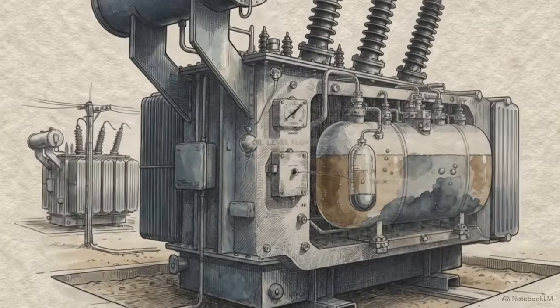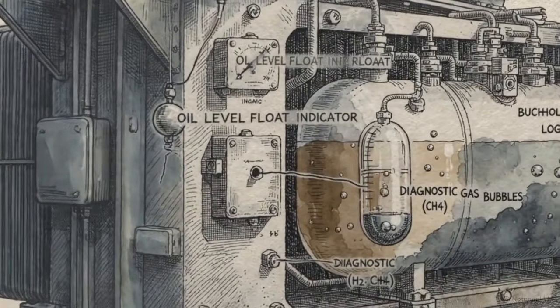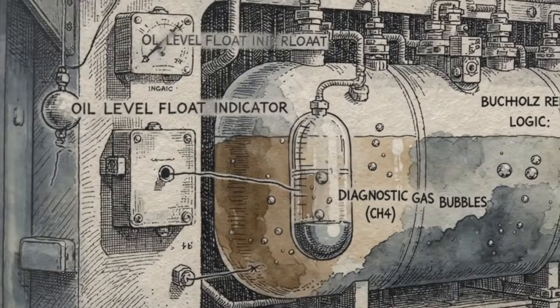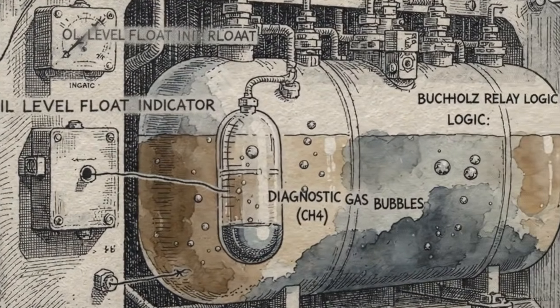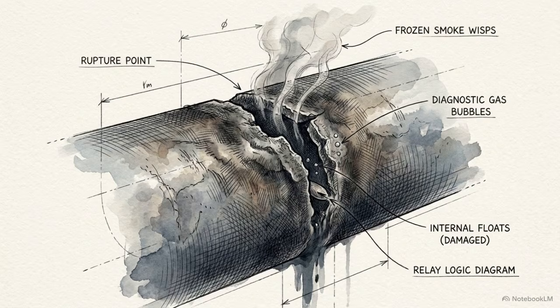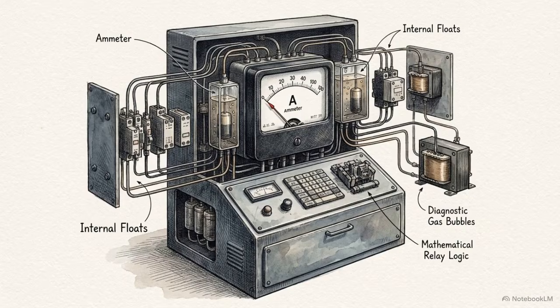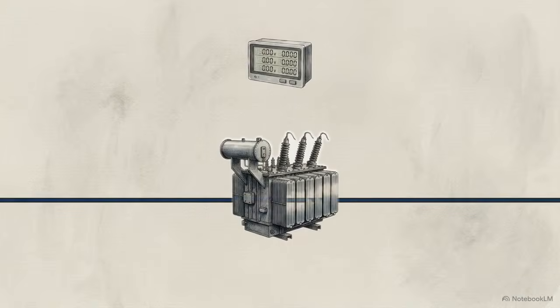Power transformers are the static, billion-dollar workhorses of the global electrical grid. But despite their massive steel construction, they can be permanently destroyed in seconds by microscopic internal failures. Traditionally, protecting these assets means monitoring their electrical current. Relays constantly measure the amps flowing into and out of the system to ensure operating limits aren't breached.